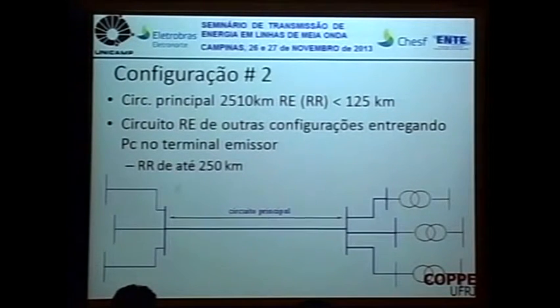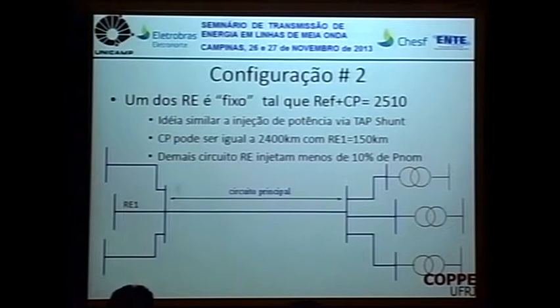This situation of the emission branch and the receiving branch, when they are smaller than 125 kilometers, I can have the other circuits delivering percentages of the characteristic power. Of course, the idea is fixated from this point on until here. This needs the minimal criteria, the minimal conditions, to be established for what would be a half wavelength line.